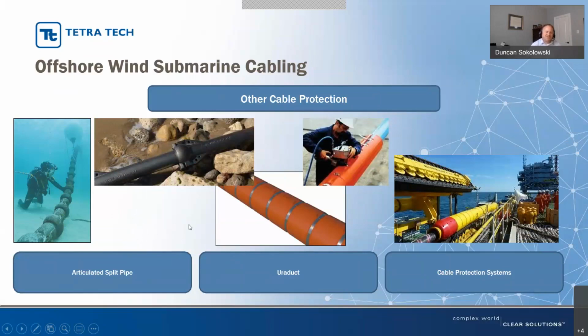As mentioned, the cable is sandwiched between two layers of concrete mattresses, but you don't normally want the mattress to lay directly on the cable. So you'd apply Uraduct, a polyurethane split system held on with stainless steel straps, applied on the ship. It gets laid down over the bottom mattress, then the top mattresses are laid on top. On the right, we have cable protection systems that generally apply where the cable goes into a J-tube at a wind turbine or transformer platform. These systems limit movement of the cable and protect it before it gets into full burial.